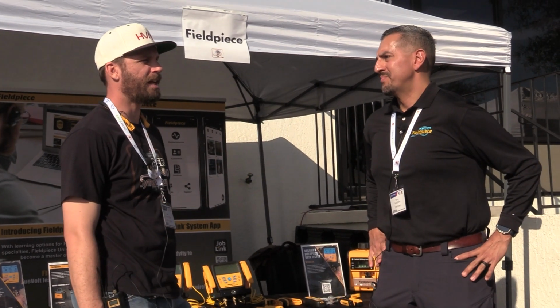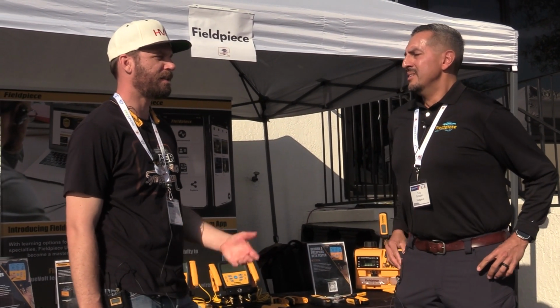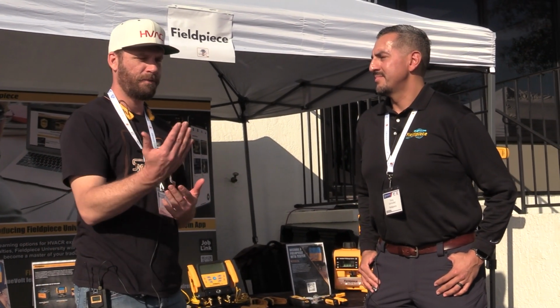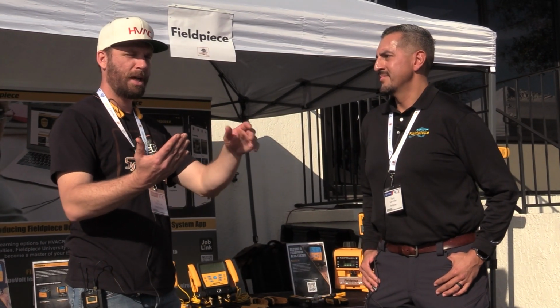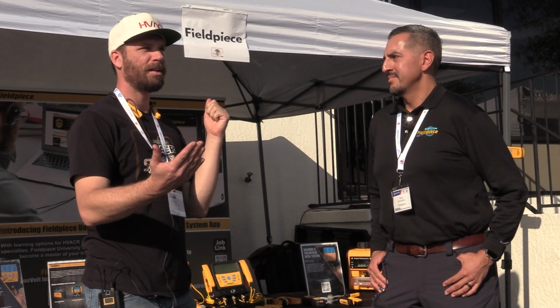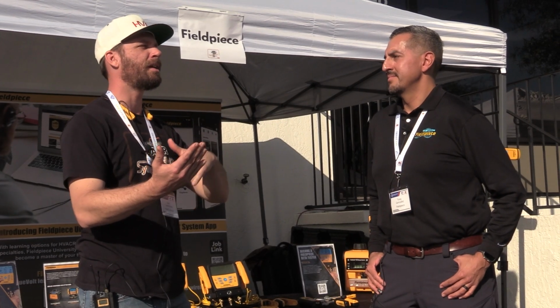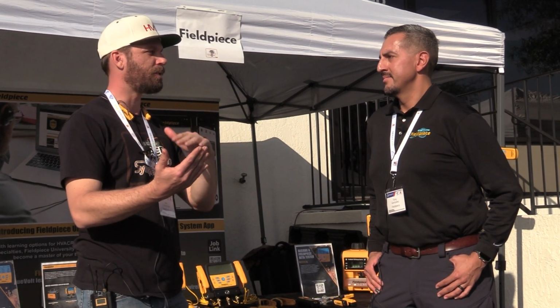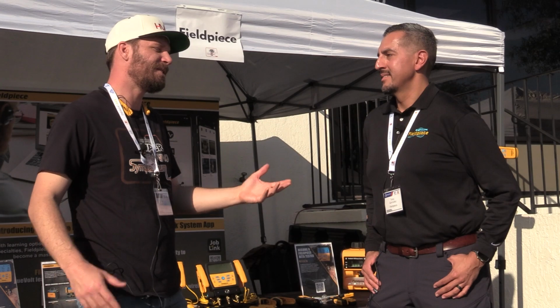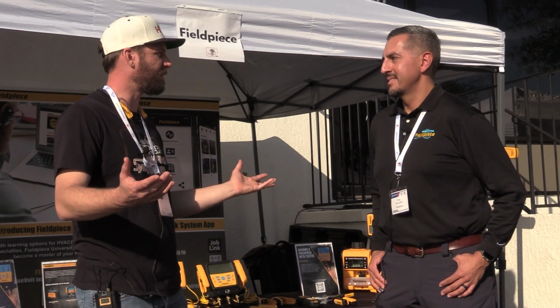Exactly what you're saying—I use it for training too. Like I'm inside at the indoor unit, I pull out my phone, look at the pressures, see what happens when I unhook the blower, and just watch your suction pressure tank, watch your suction temperature line tank. So even just for the convenience of training, it's great.